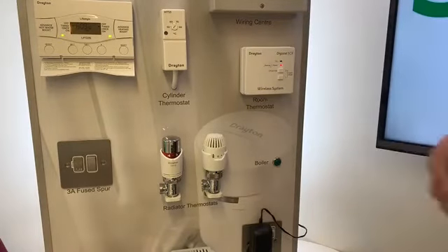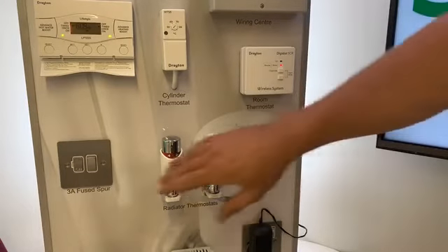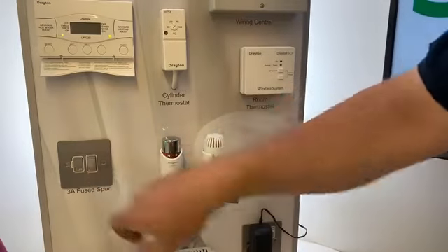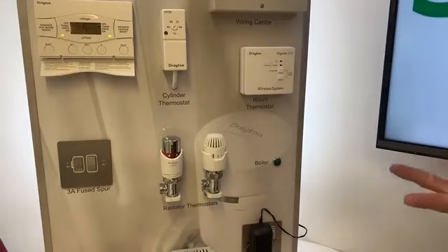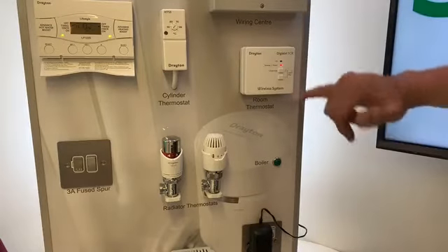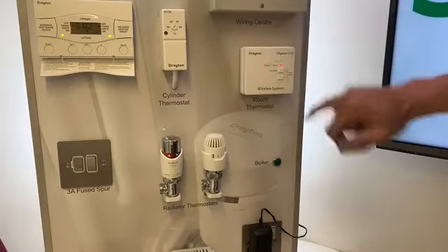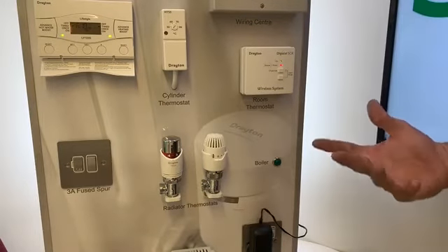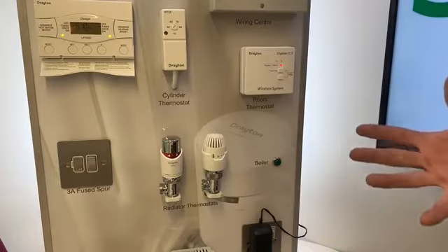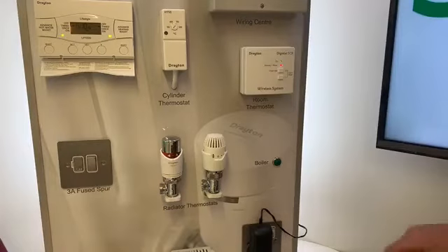But let's assume you're going through and you want to commission this. So first thing is, if it's been on for a while, power cycle it, bring it back on and wait for the alarm light to come on, which it is there. Then hit the override, make sure that you get the green light on, and also make sure that has fired whatever it is downstream, maybe the boiler, or open the valve, or whatever it is that it's doing. Make sure that by hitting that override, it's done that.